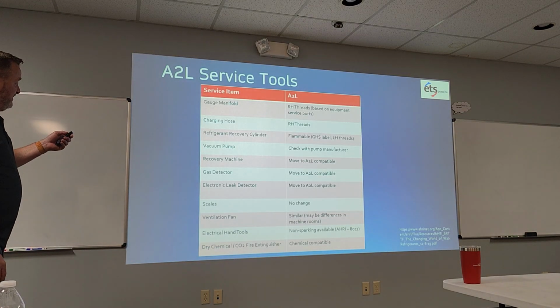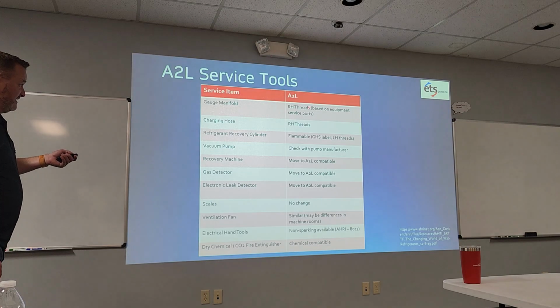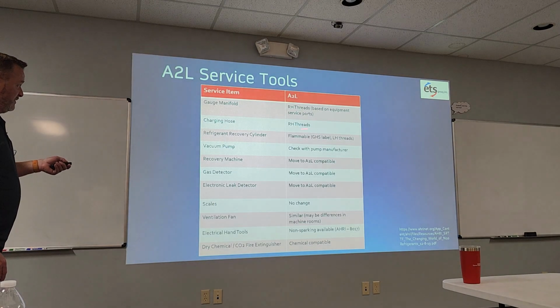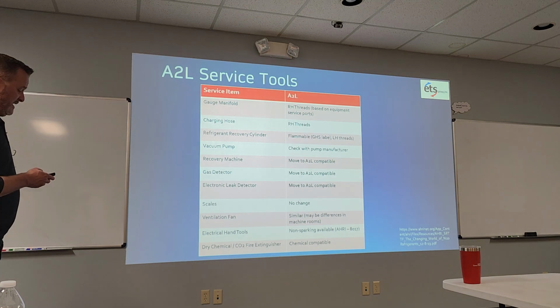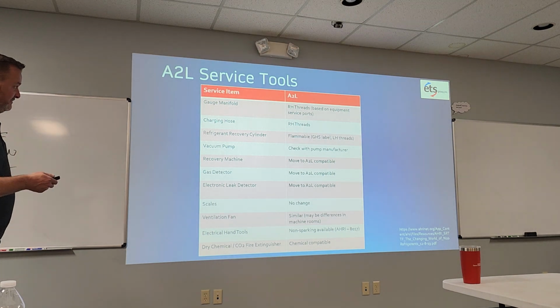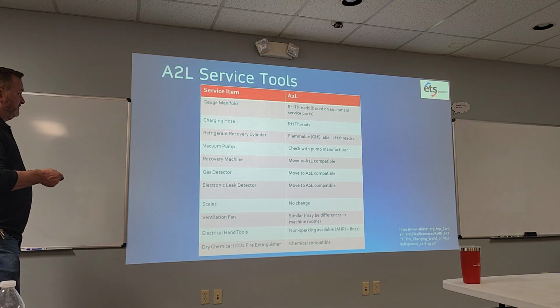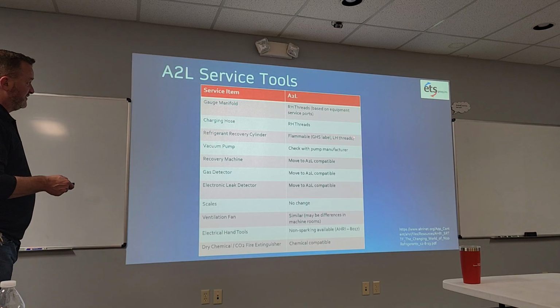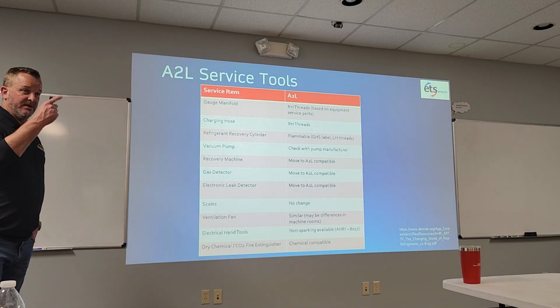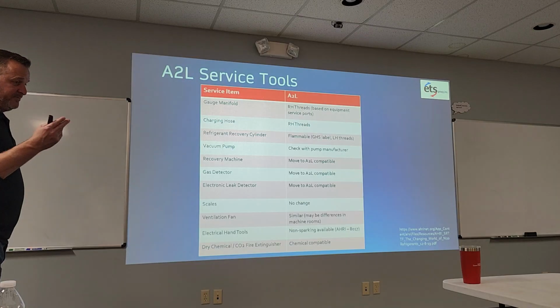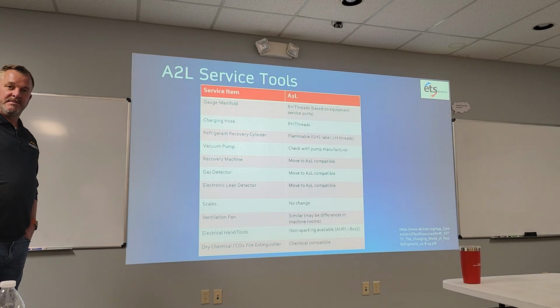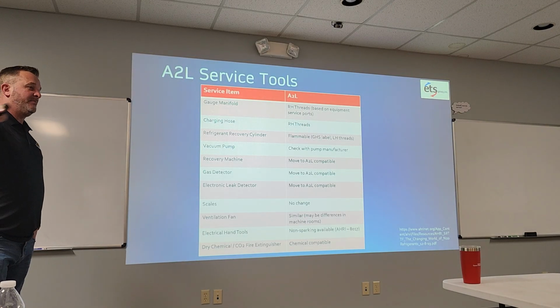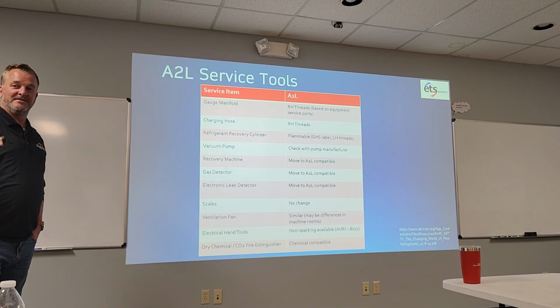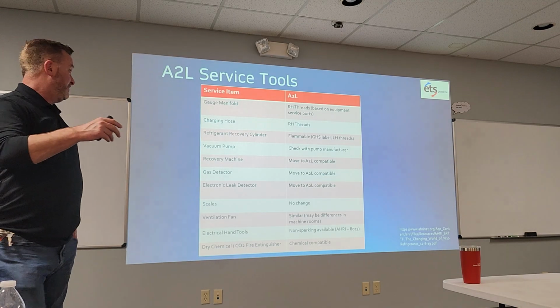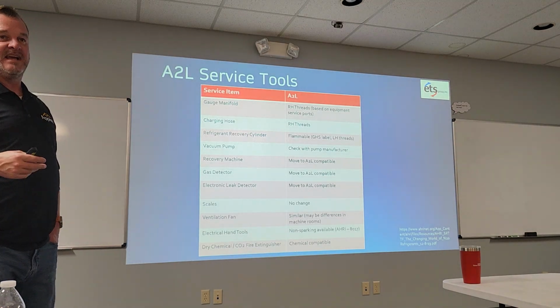So obviously all these things - you get your manifold sets, those would be right hand thread just like everything else. Your charging hoses are going to be right hand thread as well, except your adapters on the systems. Your cylinders are going to be left-hand threads, as I talked about before, with a big red stripe around them. Vacuum pumps - again, just check with the manufacturer you're using. I know you guys all use Appion, you'd never go to anything else, there's no reason to. But whatever brand you're using, just make sure it's A2L approved and certified.